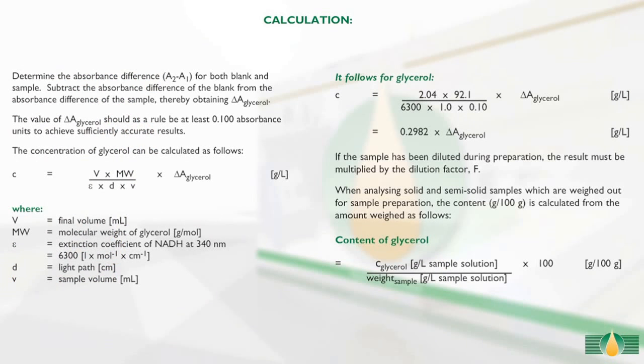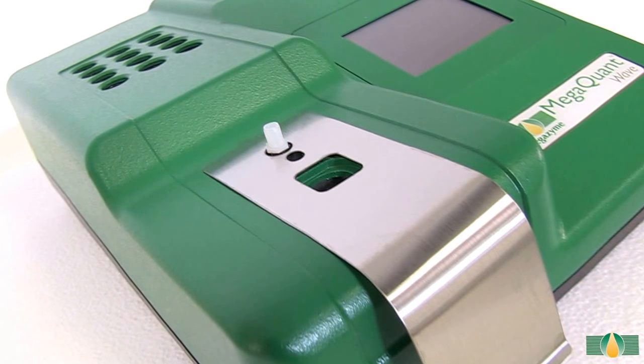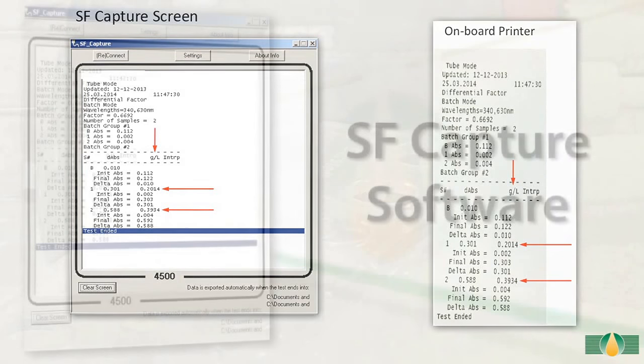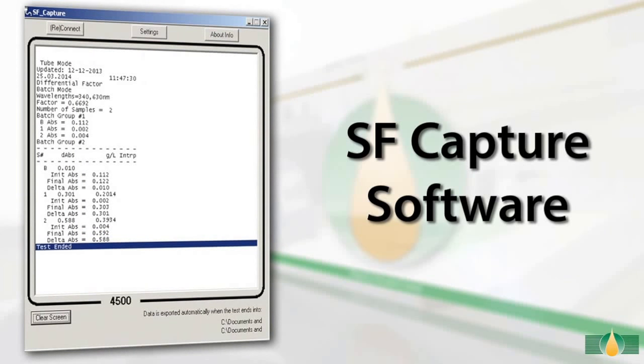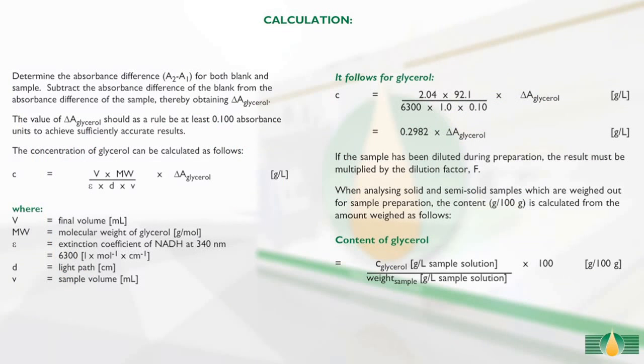The absorbance readings A1 and A2 of the sample and the blank reactions are used to calculate the glycerol concentrations in the original samples. When performing this test using the pre-installed protocol on the MegaQuant Wave spectrophotometer, the results will be automatically calculated and printed via the onboard printer, or the data can be exported to a computer using the SF Capture software. If the results output raw absorbance values for both blank and samples, the calculations of glycerol content can be performed manually as described in the calculations section of the kit booklet.